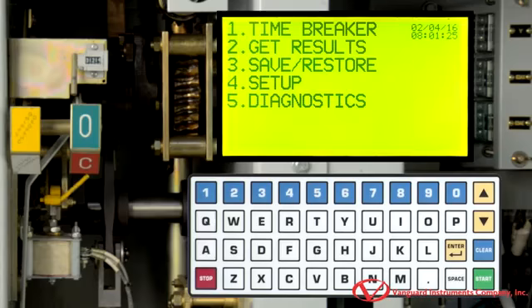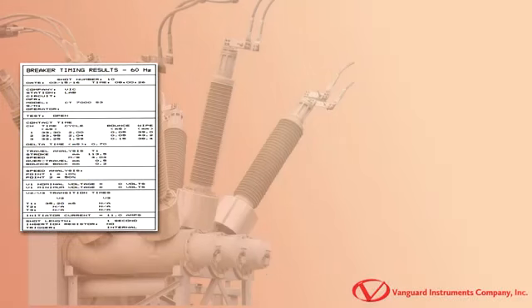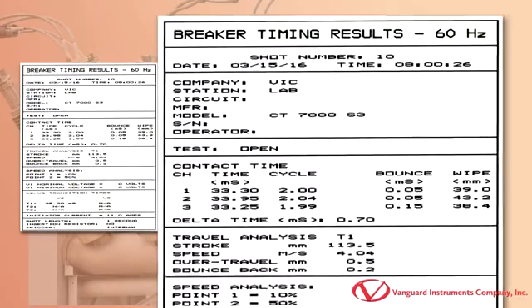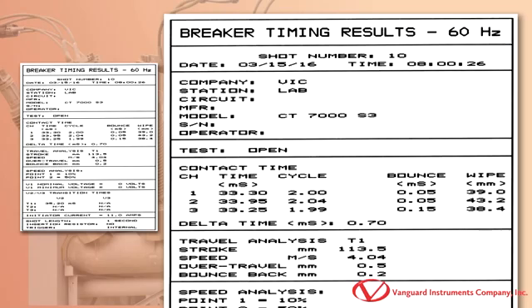Next, we will take a closer look at the test results. Here we have a sample printout of an open test shot. The CT7000S3's frequency setting is shown in the header. The frequency value is used to convert the contact time from milliseconds to cycles. Here we can see the date and time the test was performed. This header section shows relevant test information for the test record. This information is entered by the user before performing the test.